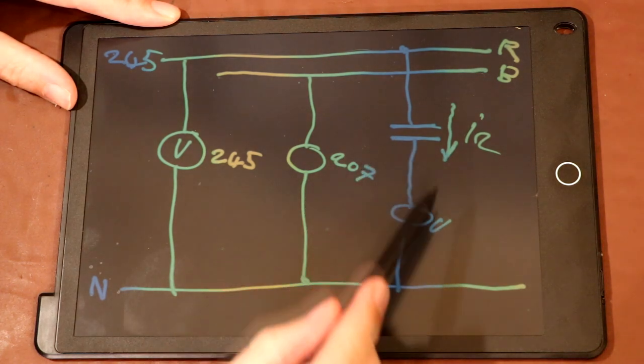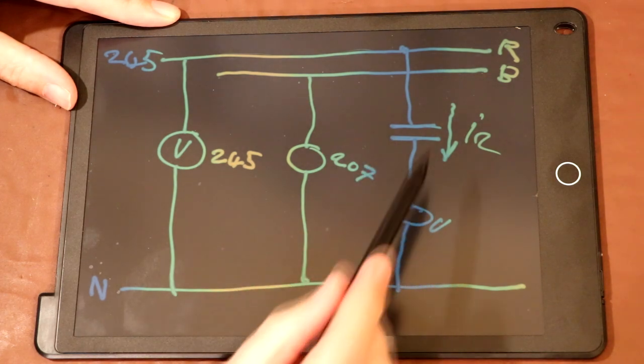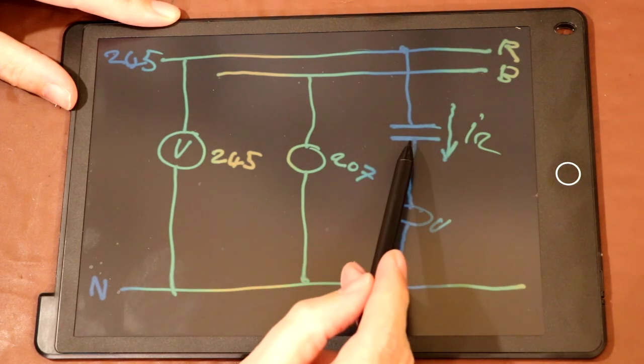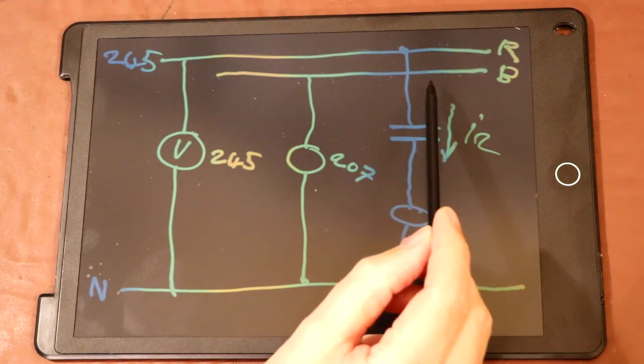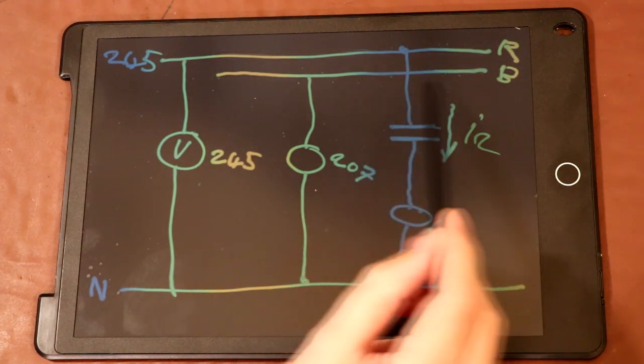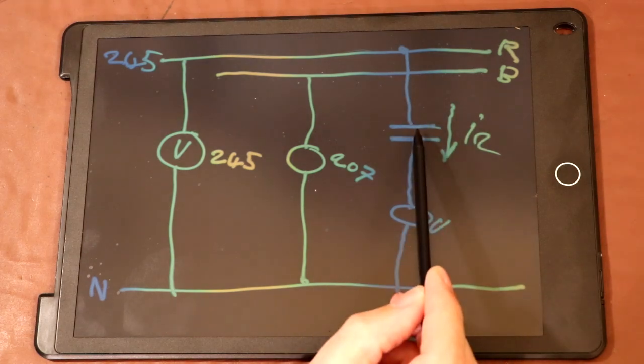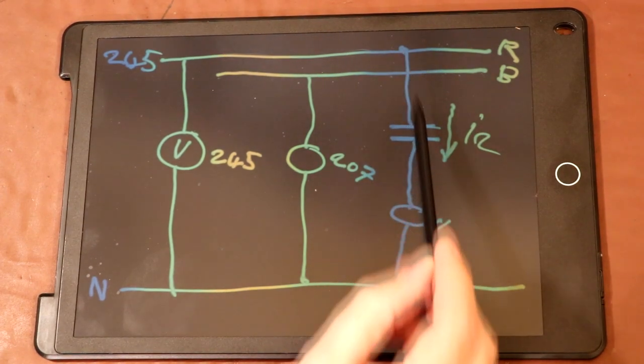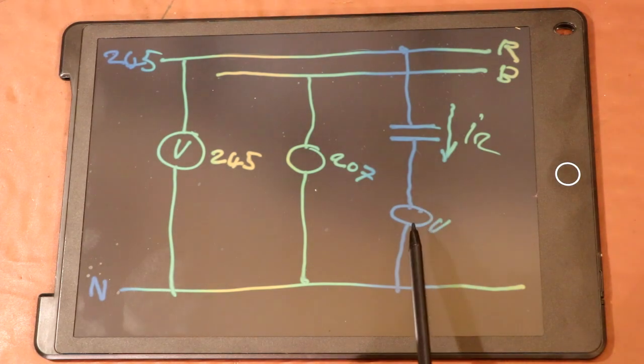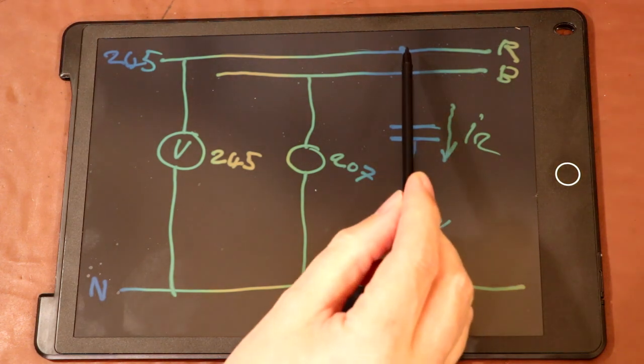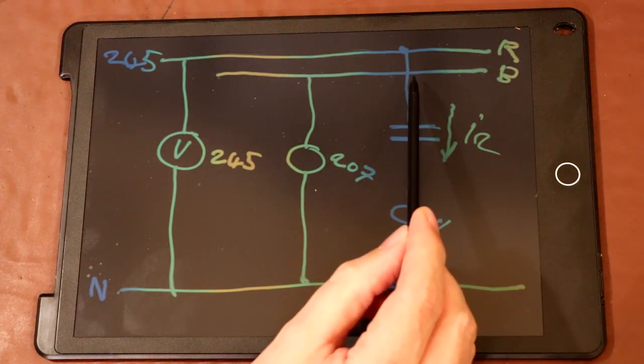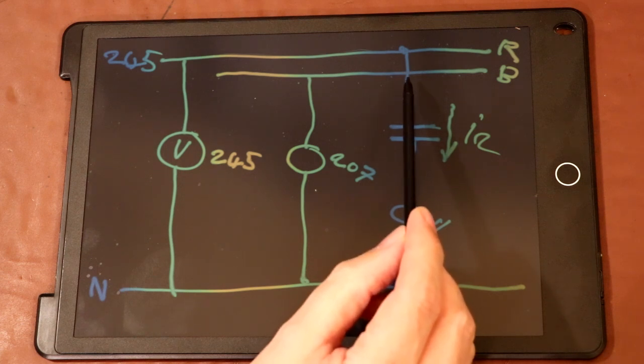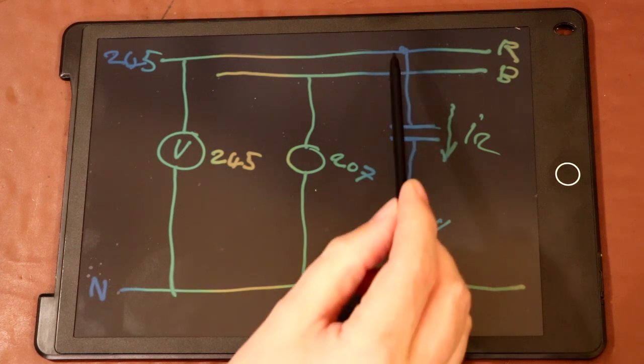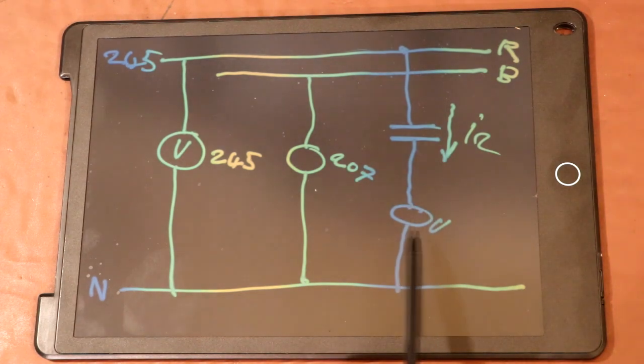Now, the magnitude of the current that's flowing in our circuit is going to be dependent on the value of capacitance. Now, if our red and black wires are running parallel with each other for quite a long distance, the value of that capacitance is going to be relatively high, and that's going to drive the current that's flowing in our circuit, and that's going to increase the voltage reading on the meter. Whereas if the distance that the red and the black wires run together is relatively short, the actual capacitor formed is also much smaller, and of course the current then flowing in the circuit will be smaller, and the voltage reading will also be smaller.